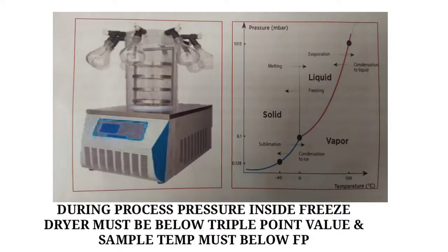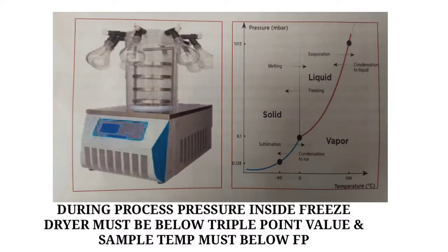Here you can see the diagram of a lyophilizer and the triple point of water. Important notice: during the process of lyophilization, the pressure inside the freeze dryer must be below the triple point value, and the sample temperature must be below the freezing point.